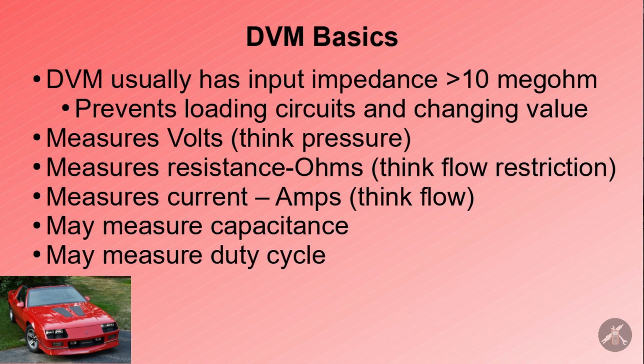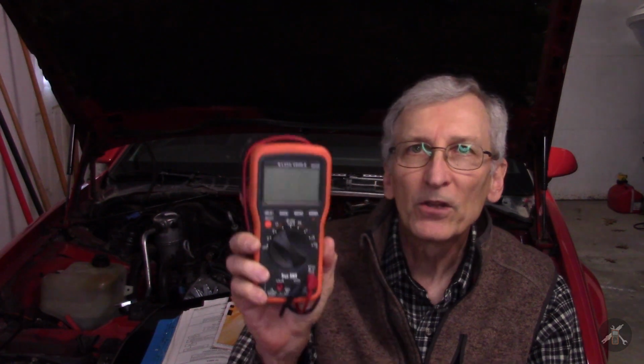The standard that controls engineers say is they usually want 10 megohms of input impedance or more. Most analog meters with standard circuitry, unless they're very expensive and sophisticated, the last one I saw was 2,000 ohms per volt or 10,000 ohms per volt, nowhere near 10 megohms. Typically, if you get a digital one, you can almost be assured it meets that 10 megohms. They'll usually say it in the specs, but even this meter doesn't say it explicitly, I think because these meters are so common.